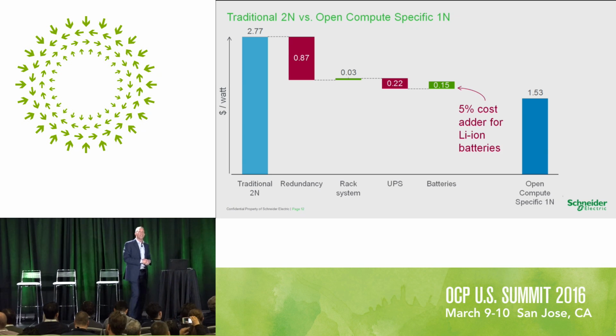The batteries in an Open Compute architecture, compared to a traditional UPS with sealed lead acid batteries, cost more because you're using lithium ion batteries. It's about 15 cents when you net it out—so the batteries actually cost more. Lithium ion batteries are still 2 to 3 times more expensive than sealed lead acid.